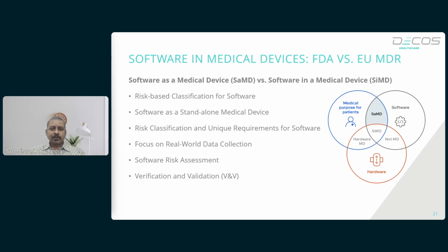SaMD stands for software as a medical device, where the software is standalone and performs medical functions without being tied to a hardware device. For example, apps for diagnostic purposes, clinical decision making, or treatment planning. SiMD stands for software in a medical device, where the software is embedded into a physical device to enhance or control its functions. For example, software in insulin pumps or MRI machines falls under this category.